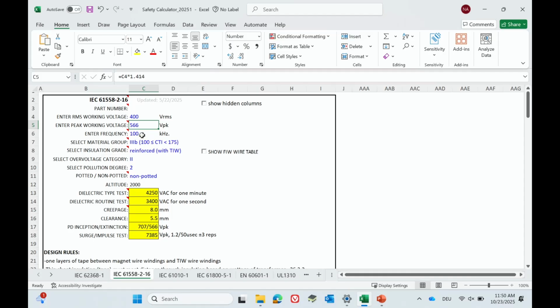If I keep the frequency of the device at 100, select material group 3, and then the reinforced level, I need 8 millimeters of creepage, for example. If I put in 500 instead, I need 10 millimeters of creepage. This is the tool we use internally to dimension how much creepage and clearance we need.